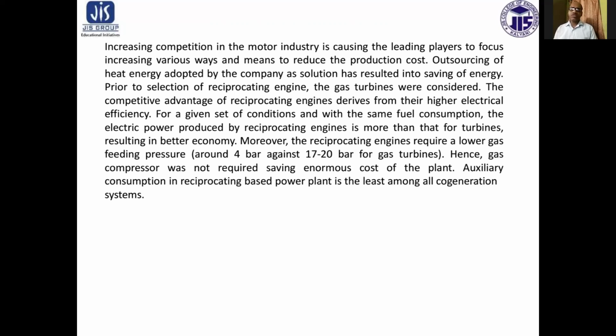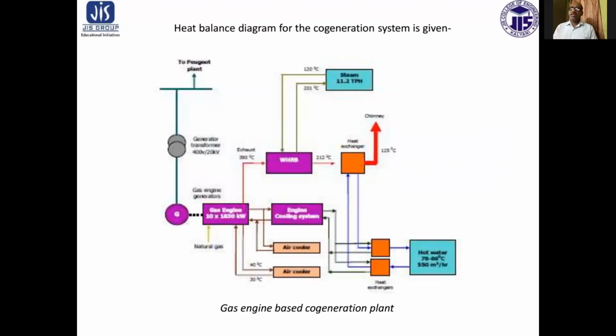Auxiliary consumption in a reciprocating engine based power plant is the least among all cogeneration systems. And this is the heat balance diagram for this industry, where the gas engine first of all draws energy in the form of natural gas, and it is producing power supplied to the Peugeot plant. The exhaust is passing through the waste heat recovery boiler to the chimney, and the engine cooling system is also producing hot water, which is used inside for conditioned air. And from the waste heat recovery boiler, steam is generated.